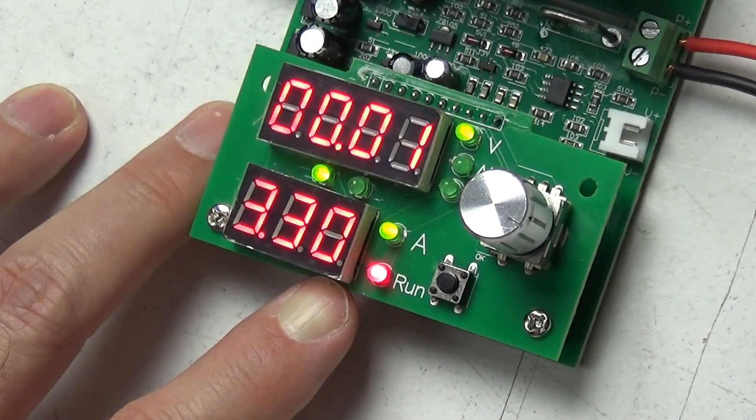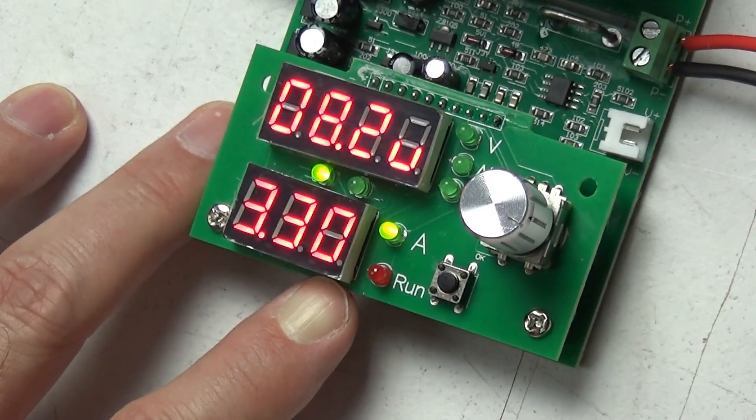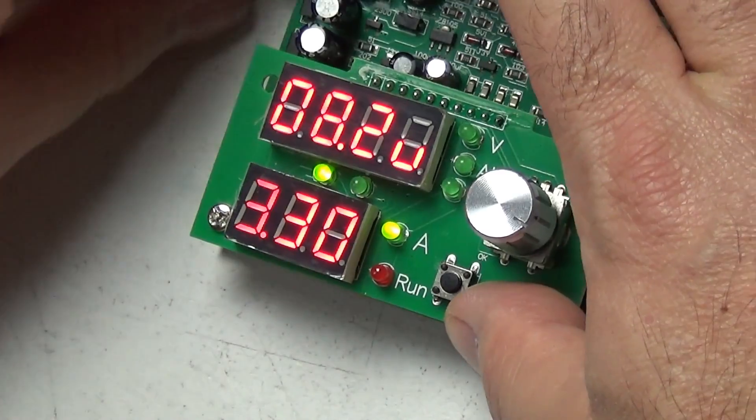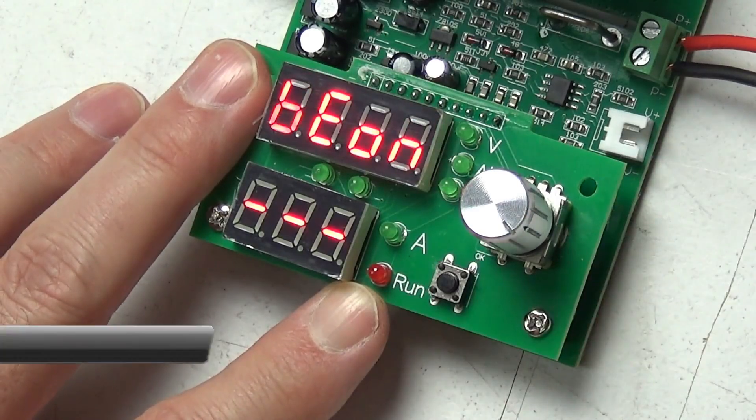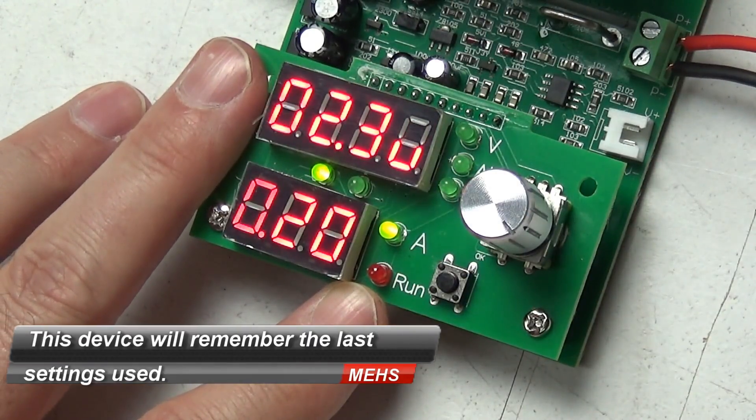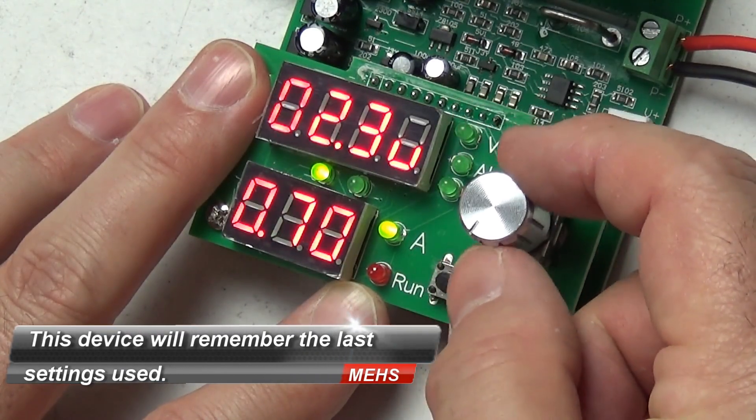So this will go all the way to 35 volts and all the way up to 10 amps, but obviously that combination is 300 watts of power. This is a maximum 60 watt electronic load, so if you are selecting something like 10 amps you can't go any higher than 6 volts. If you need a 12 volt test your maximum in this instance would be 5 amps, and it will give you a warning if you go over those limits.